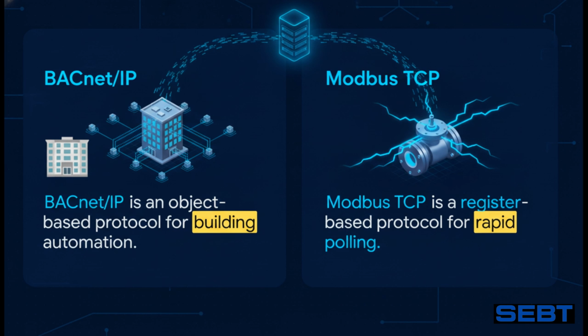Now, on the right is Modbus TCP. This is your classic industrial protocol. It's register-based, which means it is absolutely fantastic for rapid polling of live data points. Like if you need to quickly grab the exact speed of a fan or the exact position of a valve, Modbus is your best friend. Both of these protocols ensure that live values and data packets move seamlessly from the PLC switch all the way up to our server.